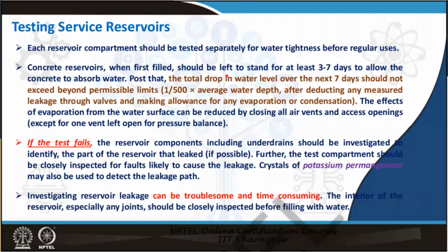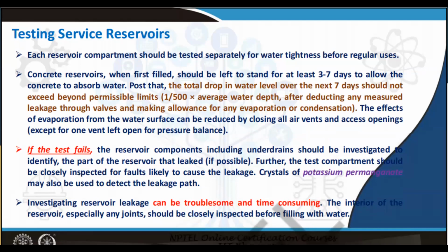So here you can see this is the test for a concrete reservoir. It should be left to stand for 3 to 7 days for the concrete to absorb the water, more like a curing process. And then in the next 7 days, the total drop in the water level should not exceed 1/500 of the average water depth after deducting any measured leakage through valves and making allowances for evaporation or condensation.